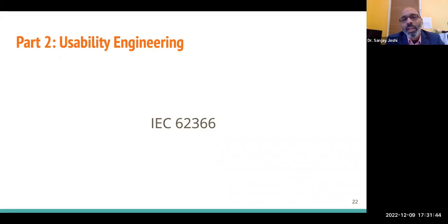If your device is not a medical device, many of these things may not even apply. But if you consider it a medical device, and more importantly, if the government considers it a medical device, then at least three things apply: 13485, the quality management system that we covered in the last talk, 14971, risk analysis, and 62366, usability. Depending on whether you have software or hardware, other standards might apply. But my gut feeling is, if you are going to make a wearable device that is supposed to be for medical use, all of these apply. Does that answer the question?